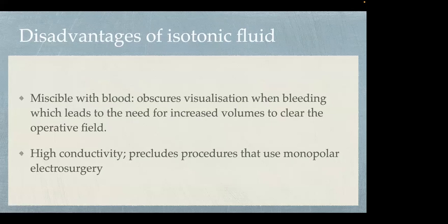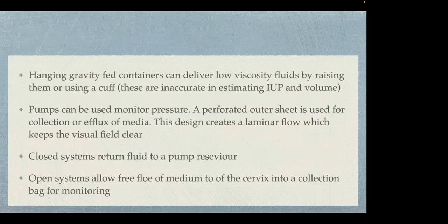And because saline and Ringer's lactate have high conductivity, we cannot use monopolar. There's a special monopolar that we can use, but I forget the name. But other monopolar we cannot use because of the high conductivity.